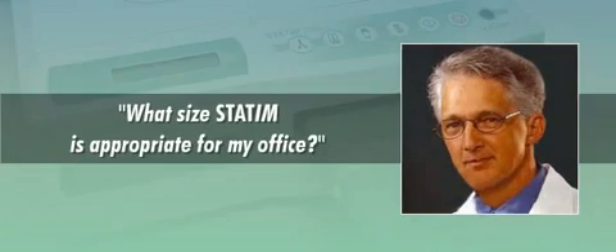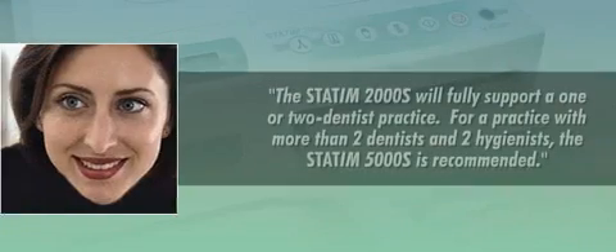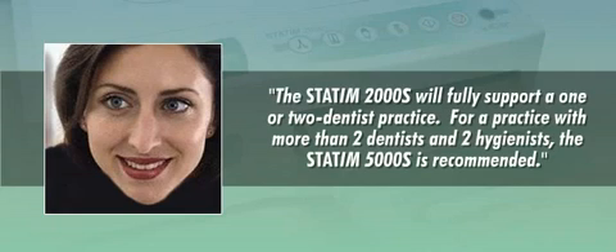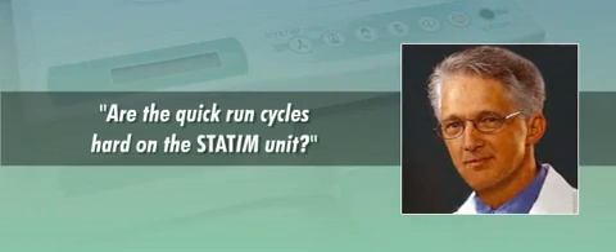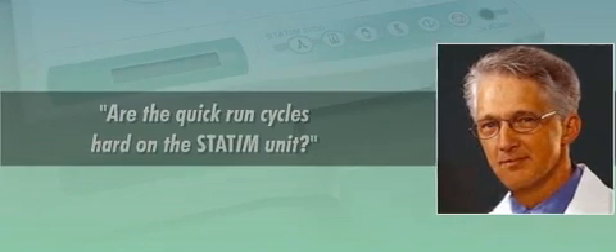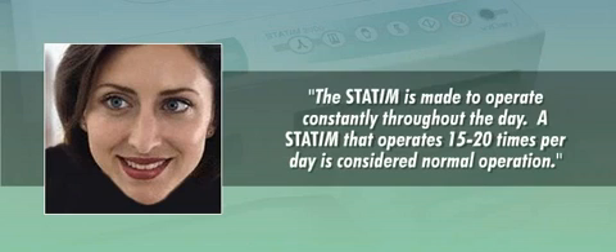What size STATIM is appropriate for my office? The STATIM 2000S will fully support a one or two dentist practice. For a practice with more than two dentists and two hygienists, or where larger implant instruments are used, the STATIM 5000S is recommended. Are the quick run cycles hard on the STATIM unit? The STATIM is made to operate constantly throughout the day. A STATIM that operates 15 to 20 times per day is considered normal operation.